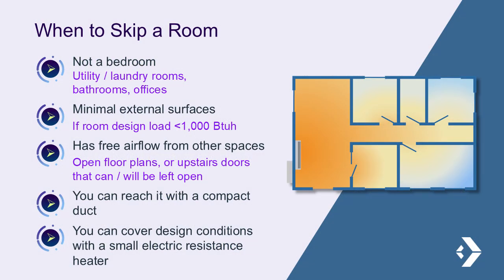In the spirit of zoning designs, let's establish something important. Not every room in a home requires a dedicated heating or cooling system. Know when to skip a room. Spaces like utility rooms, bathrooms, or home offices often have minimal external surfaces, resulting in low heating or cooling loads. If a room's design load is less than 1000 BTUH, it can often be excluded from the system. Similarly, rooms with free airflow from adjacent spaces, such as open floor plans or areas where doors are typically left open, may not need their own system.